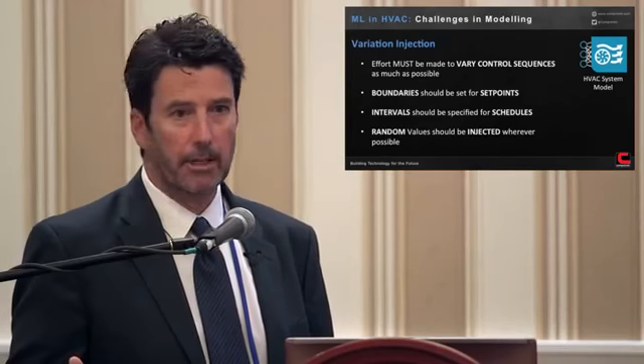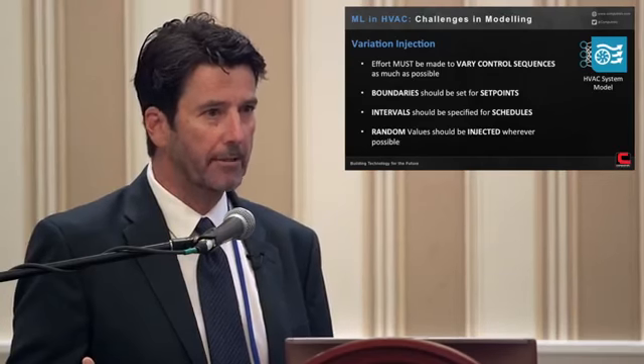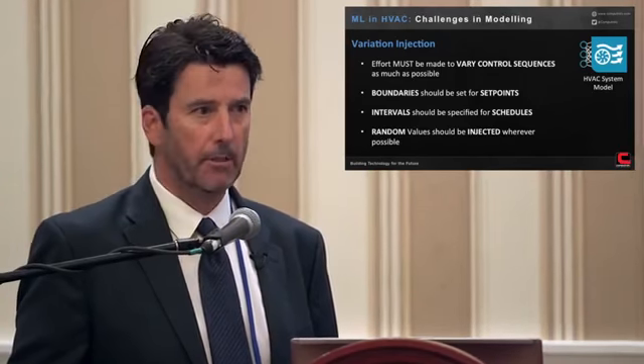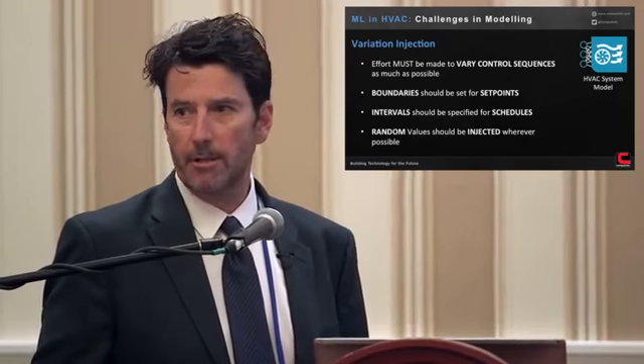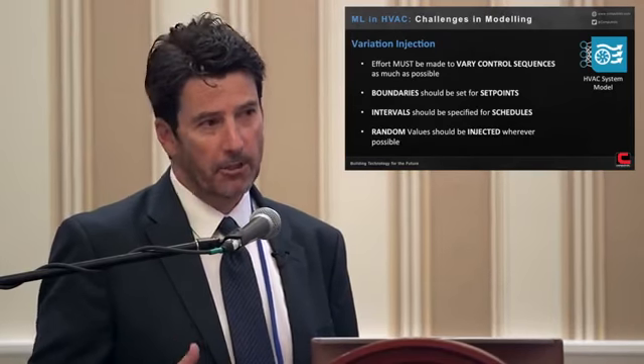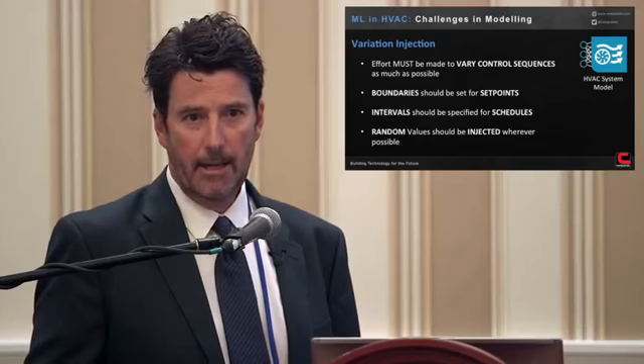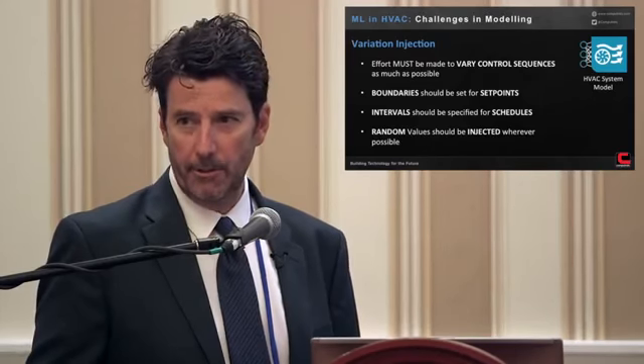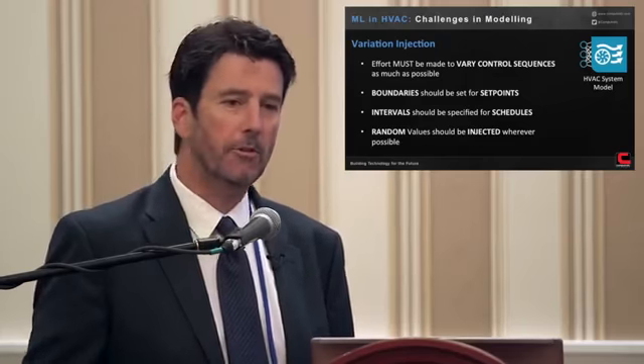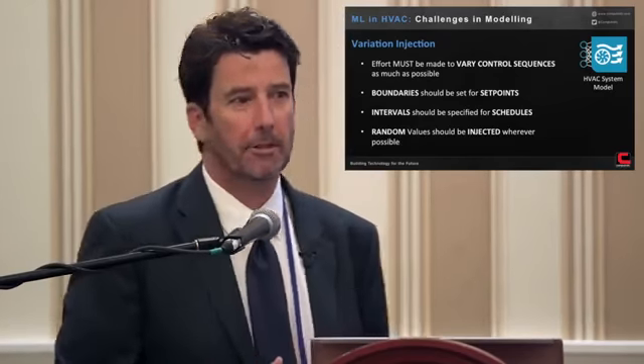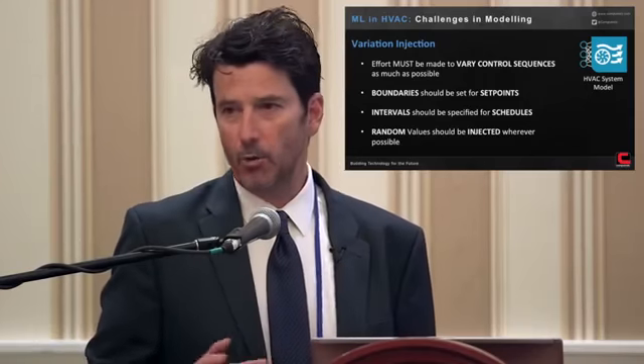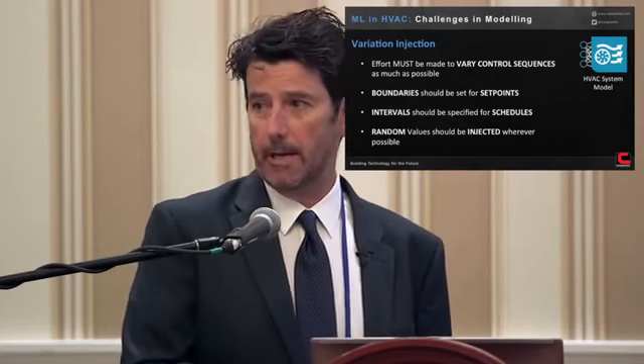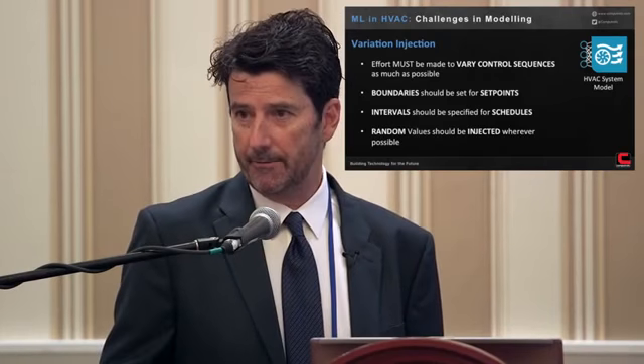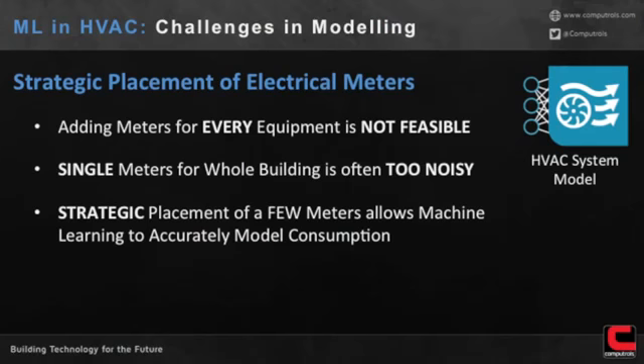Another one would be loading up a chiller. I don't know how many of you guys are engineers or get involved in that type of thing, but let's say a tenant comes in early in the morning and you have to start his air handler. Well, you got to start a chiller to make that air handler happy. And if you don't start more air handlers, you're going to freeze the chiller up. You just have to load the chiller. So you just say, okay, I got to start a bunch of more units too early. We found that's a great opportunity to randomly choose other air handlers so that every day we're building history with different air handlers, and then the machine learning can start to really sink its teeth into it and get a better model. So there's a lot of opportunities like that, and we're trying to identify those.